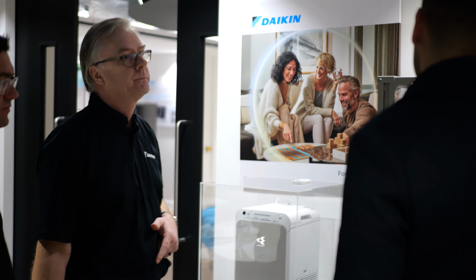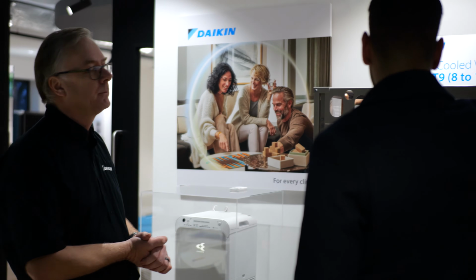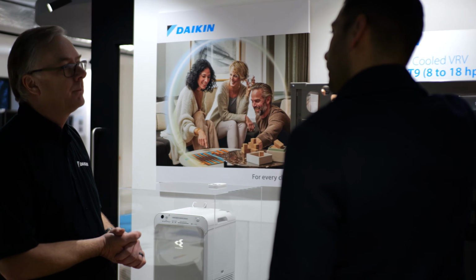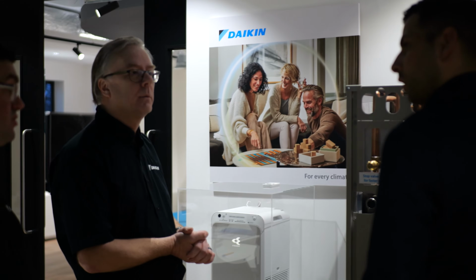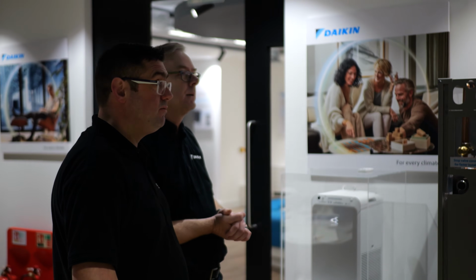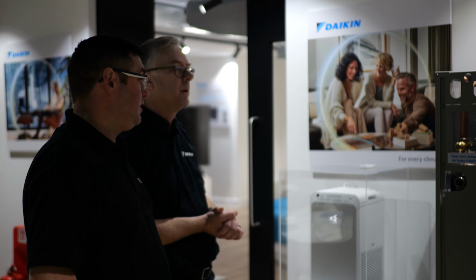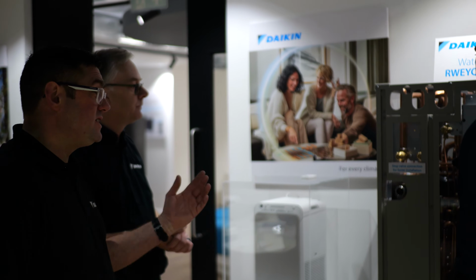Yeah, wicked. Technically a water-cooled VRV, so I don't know if... so we've done water-cooled. Just to confirm, for my knowledge, this needs to be connected to boreholes, is that correct? No, any sort of centralised loop, chilled loop, heat loop, whatever, as long as it falls within the specs of the water temperatures and flow rates, it can be used in any centralised system. Shopping centres are a good example.